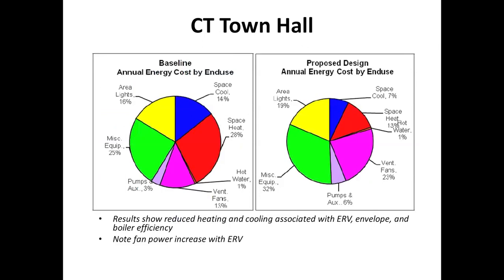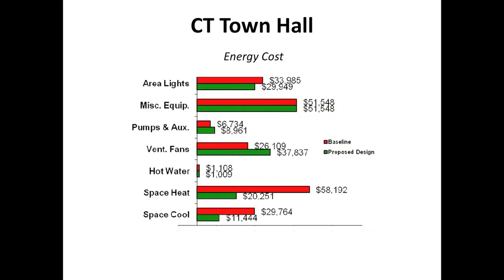Looking at these two pie charts, space heating was reduced as a percentage from 28 to 13%. Ventilation actually increased in this building because we used energy recovery ventilators, but those ERVs allowed us to reduce the space cooling load from 14 to 7% and space heating from 28 to 13%. From a cost perspective, a few categories like pumping and fan energy increased, but the reduction in heating and cooling more than made up for it.